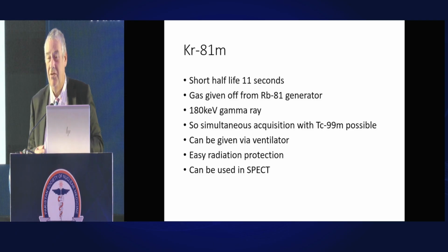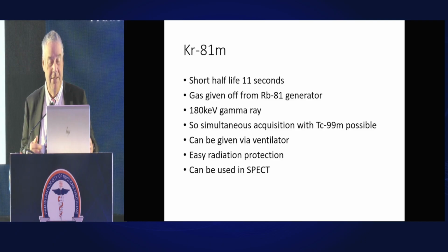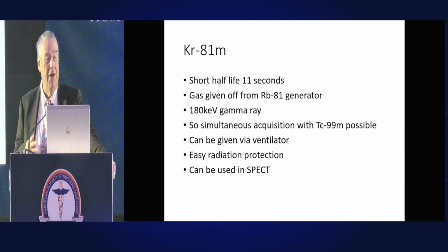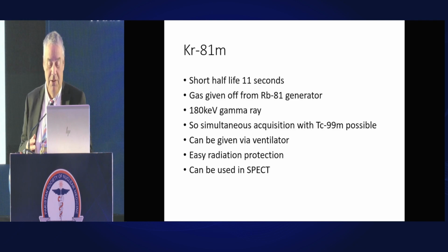So effectively, you strap the patient to the generator and you pump through either air or oxygen so that the patient will breathe that in. The radiation protection is very simple, because by the time the patient breathes it out, with the 13-second half-life, it's all disappeared. And it's very good with SPECT.